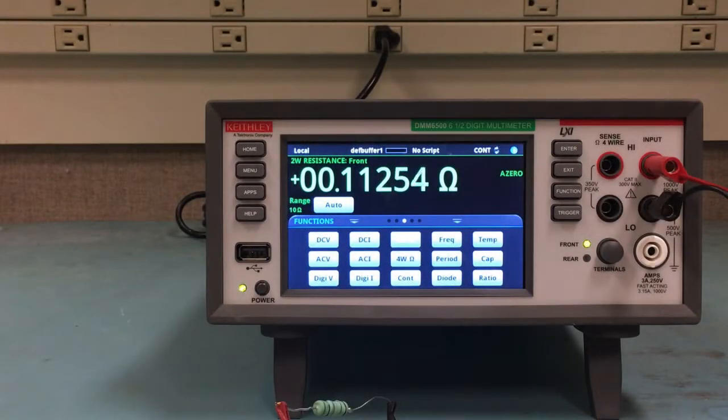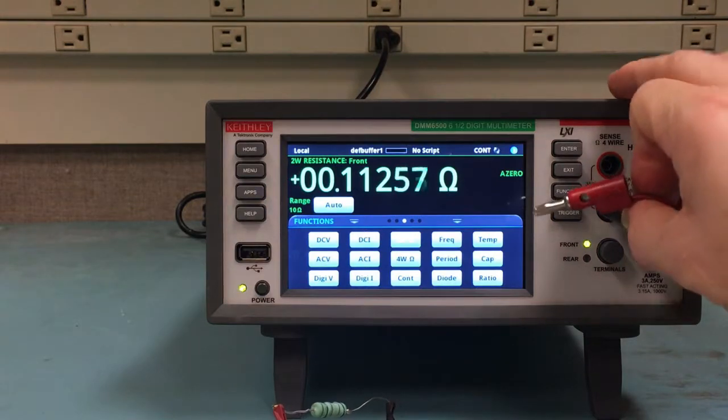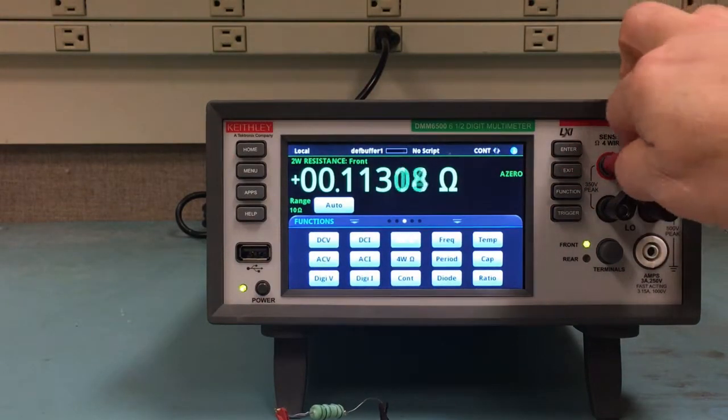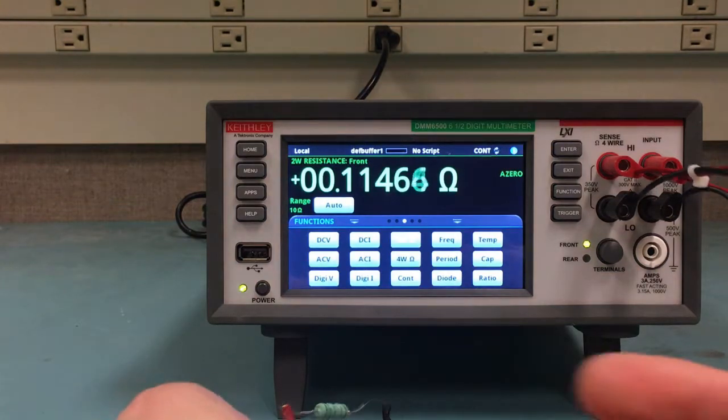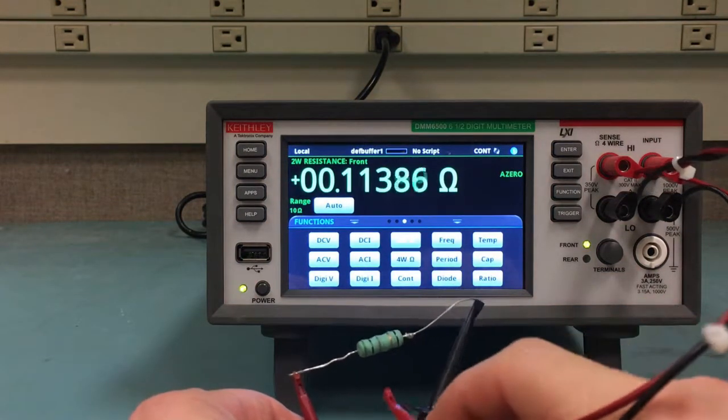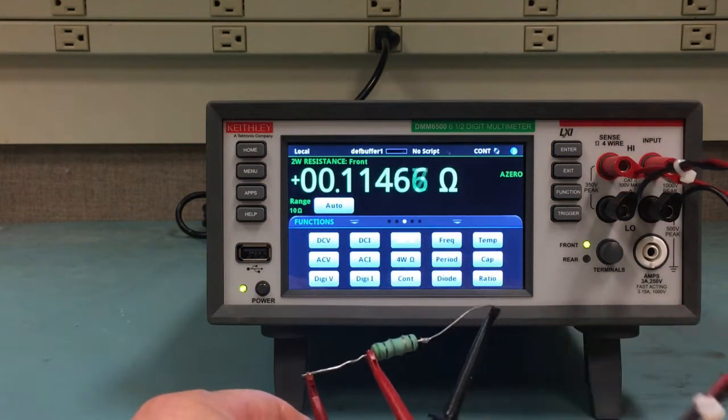Let's perform the four-wire measurement. The first step is to connect my second set of leads to the sense inputs on the front of the DMM6500. I then use those leads to clip very closely to the resistive body of my device under test.